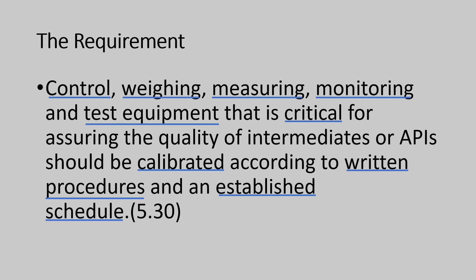Coming to schedules — how do you decide on the frequency of schedules? There are two basic approaches. The first is as recommended by the equipment supplier. There should be a clear, written, documented recommendation by the equipment vendor that the equipment could be calibrated once in the defined period.